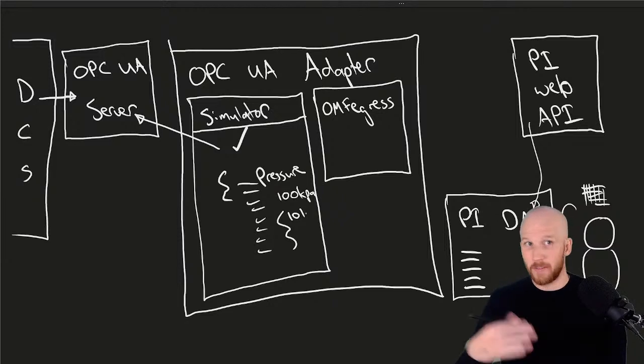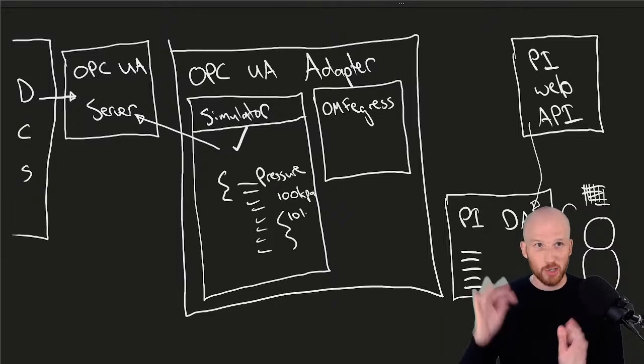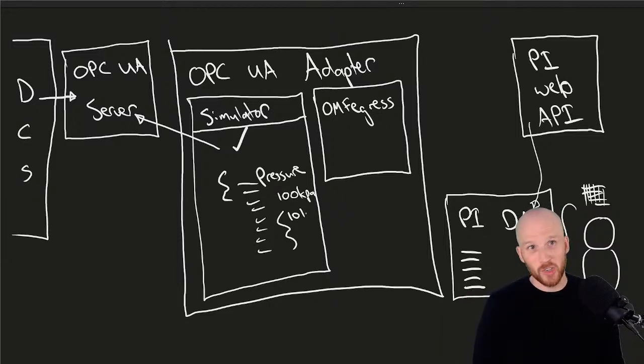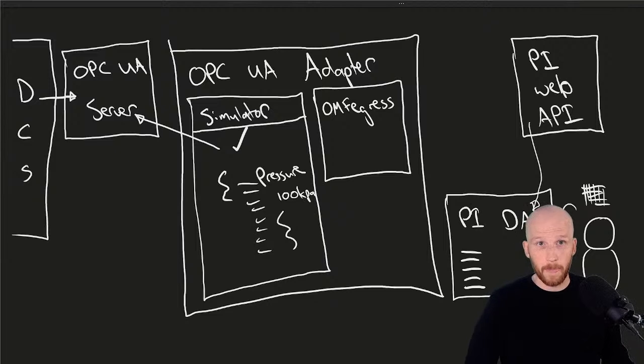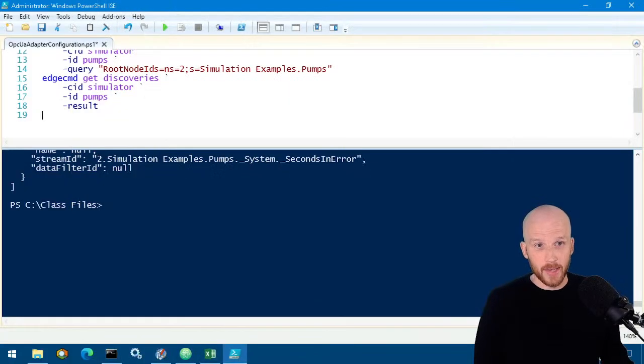But the sensitivity of our instrumentation is only to the nearest 5 kPa. Do we want to store that 101? Do we want to bother sending it? We can filter it out. We can add in a deadband here if we want to. So the equivalent here, if you're familiar with interfaces, is we're going to set up exception. And we do this again on the adapter side if we're using adapters. So let's take a look at the data filters we already have.